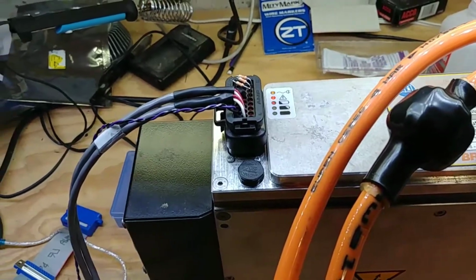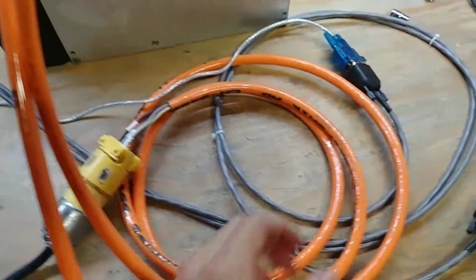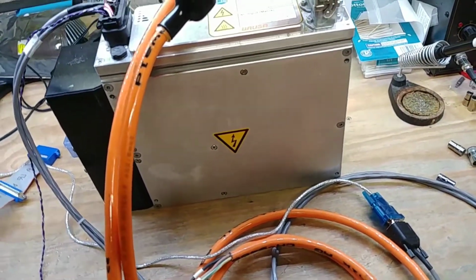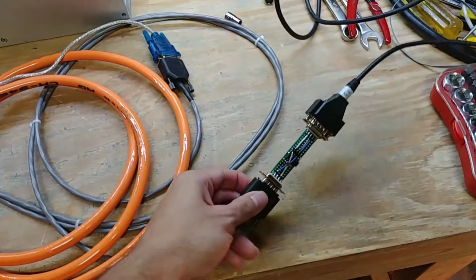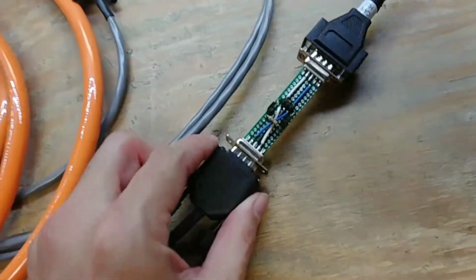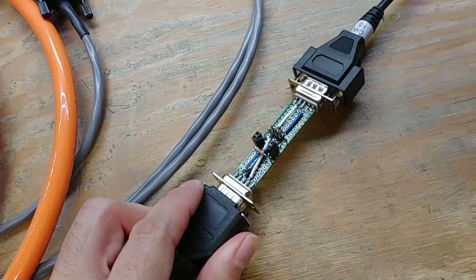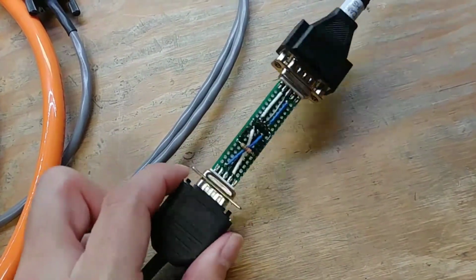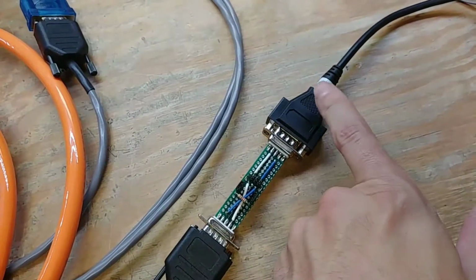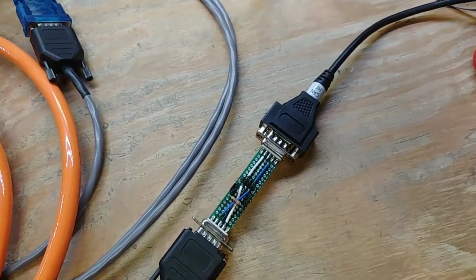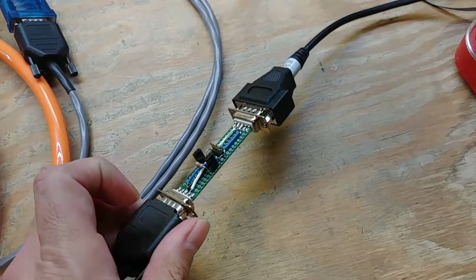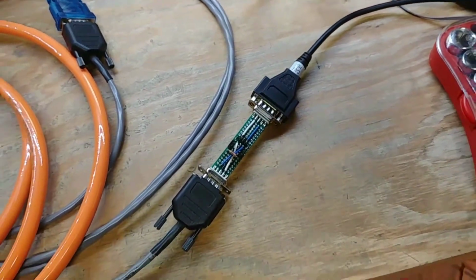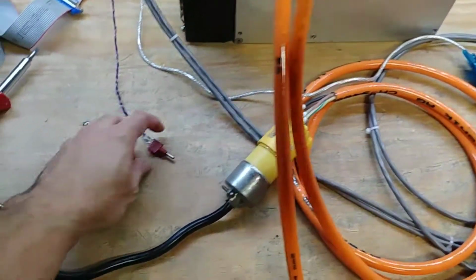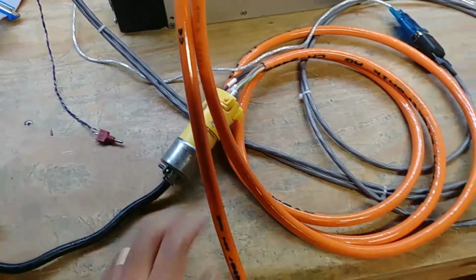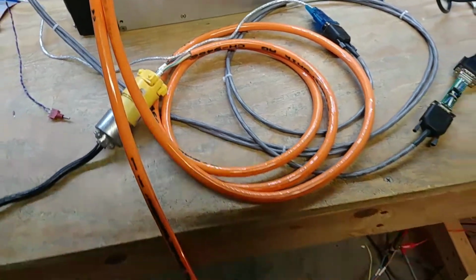Not related to the CAN problem it was having. So I've got serial going off over to the ChargeStar program so we could set it up in CAN mode, and I've got the other cable going over to my CAN bus adapter. This has the termination resistor in here, 120 ohms, and a couple jumpers. I can pop that in and out. It's just for going between a standard CAN connection to the Kvaser CAN connector. There's a couple pins on there so I can hook up the scope to probe it if needed. I also have the enable switch plugged into mains power, running off 120 volts AC.